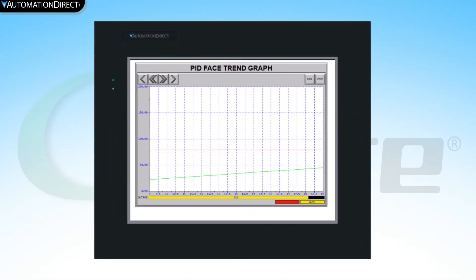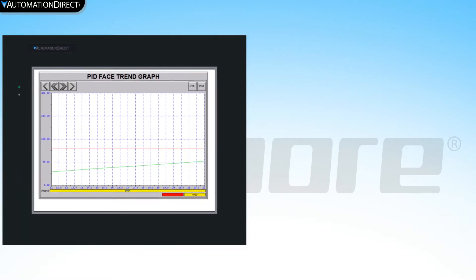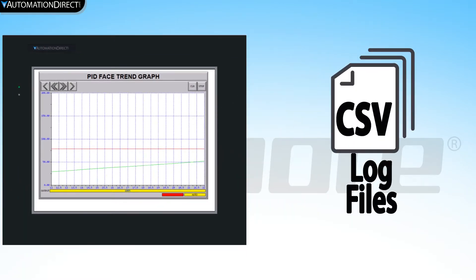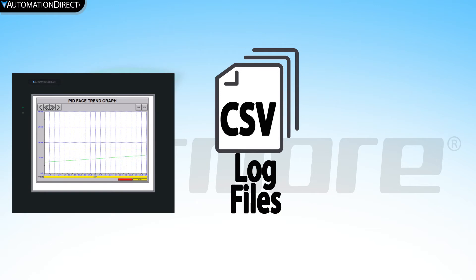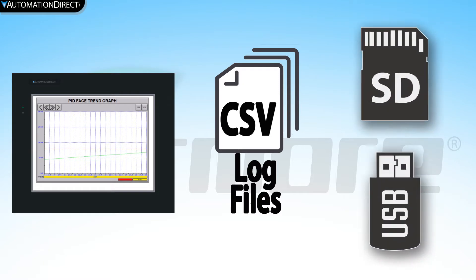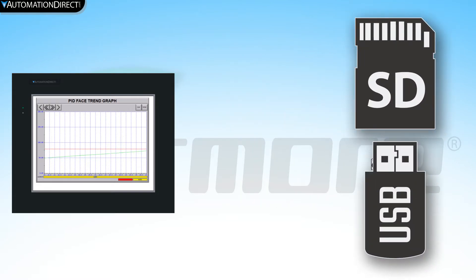With the C-more HMI, you can log data from the PID faceplate line trend graph into a CSV file. This file logs for 24 hours and a new file is created each day at midnight. The file can be stored on an external USB or SD drive.